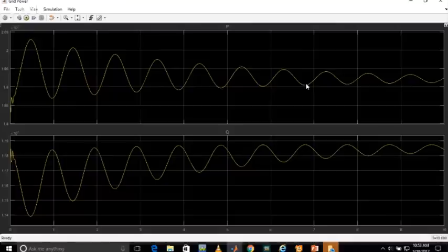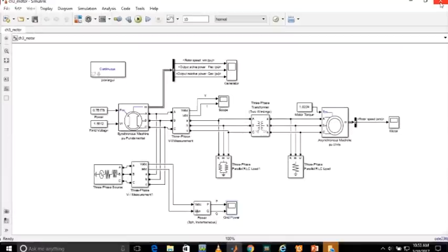As you have already known, 19 megawatt active power is provided by our swing bus. So it's coming around 19 megawatt. And similarly, how much reactive power? It's coming around 11.8 MVAr. So this is showing the exact result that is coming in our circuit. By doing the load flow analysis, the whole circuit will initialize in a faster way.